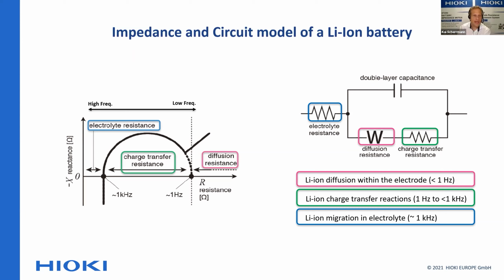If you look at the little graph on the left of this slide, you can see what's called a Cole plot, or basically a Nyquist plot. You can see the reactance over the resistance, and then you do a frequency sweep. This is electrochemical impedance spectroscopy, meaning you sweep frequencies. Typically with lithium-ion batteries it's from 0.1 hertz up to about 1 kilohertz. Within that range is where you find interesting information about the cell.